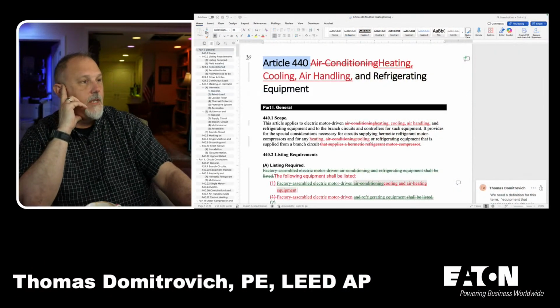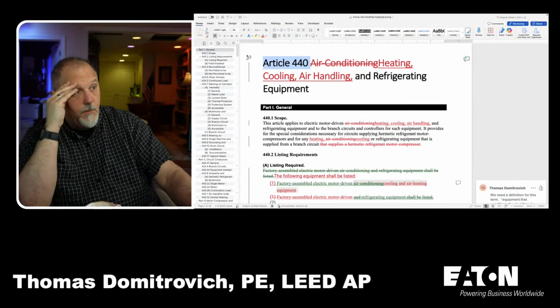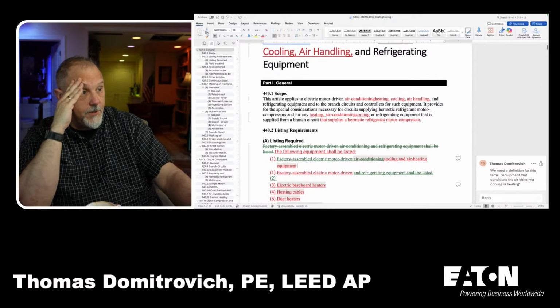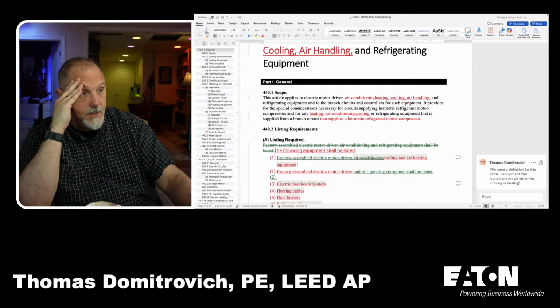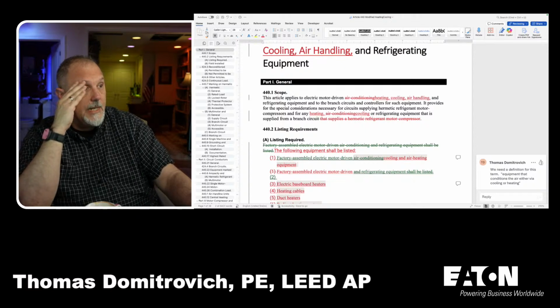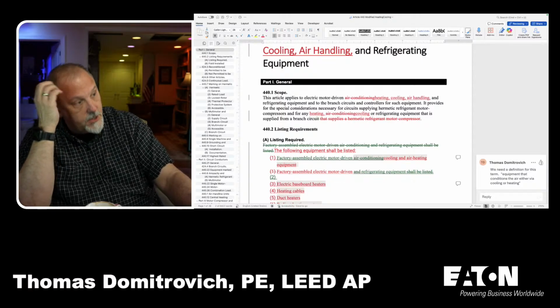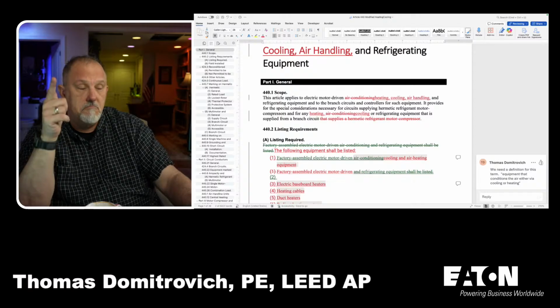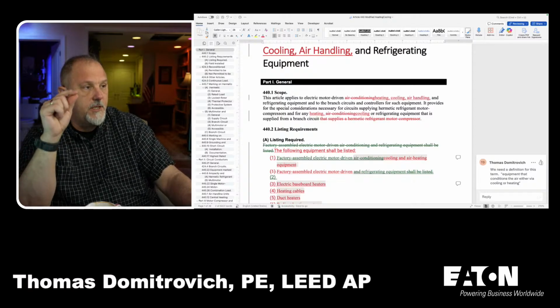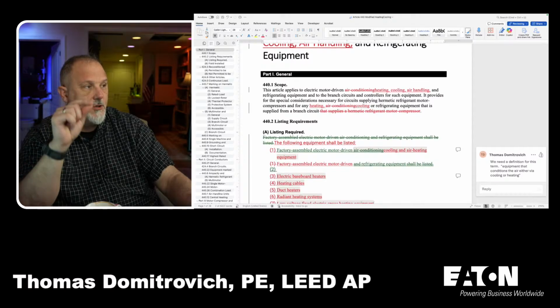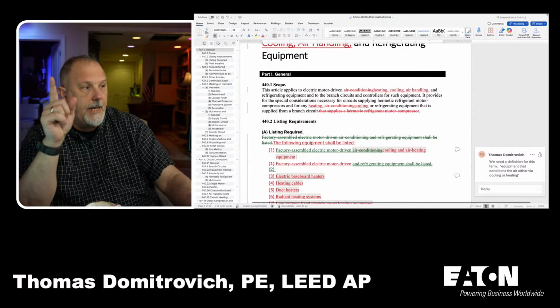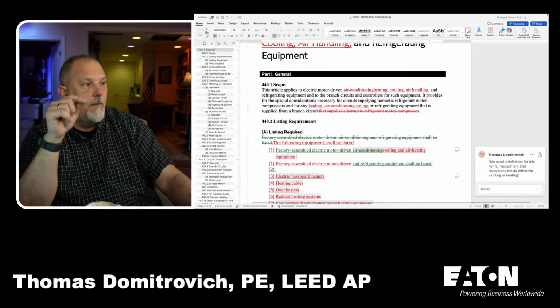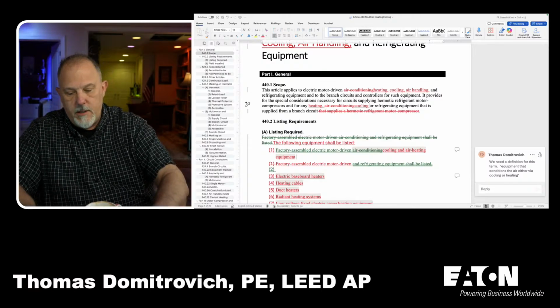All right, so I have Article 440, heating, cooling, air handling, and refrigerating. So my scope has to reflect that. This article applies to the electric motor driven heating, cooling, air handling, and refrigerating equipment, and to the branch circuits and controllers for such equipment. It provides for the special considerations necessary for circuits supplying hermetic refrigerant motor compressors and for any heating, cooling, or refrigerating equipment that is supplied from a branch circuit.